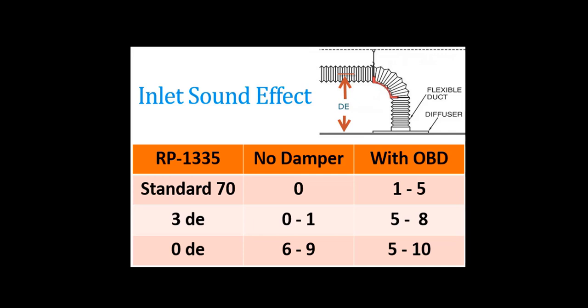We encourage you to resist the practice of putting a damper on everything and instead evaluate if one is really necessary. If it is necessary, consider putting it further up the ductwork instead of right behind the diffuser, if this is a sound sensitive application.